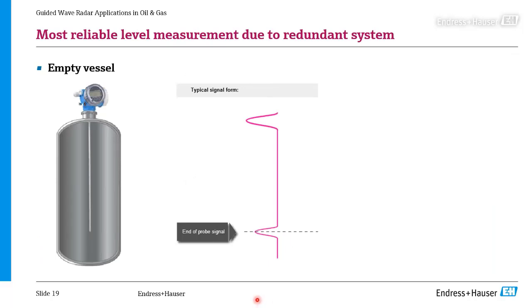Then what you might also not know is that we actually have a redundant measurement signal on the same probe of a guided wave radar. So normally we emit a signal from the top, a radar signal like Matthias described in the beginning. And when we have a change in dielectric between the gas phase, the air, and then the oil, you get a small reflection back, and we calculate the time and the distance. But what you do not know is that we actually have a secondary measurement principle on the same probe, and that's called the end of the probe signal.